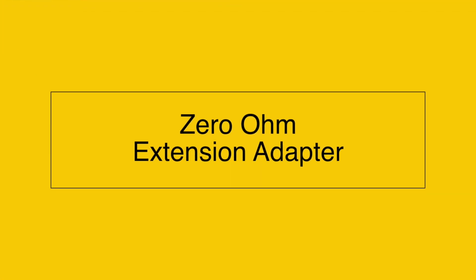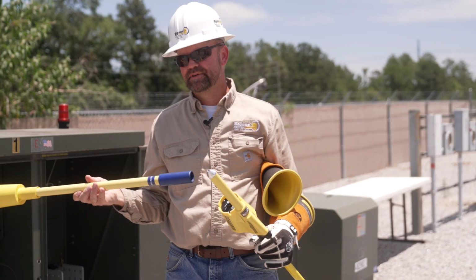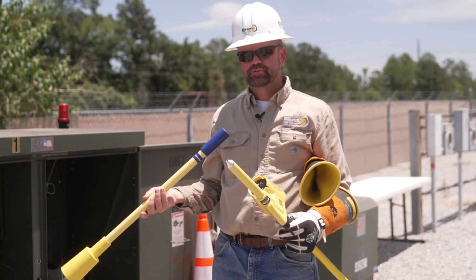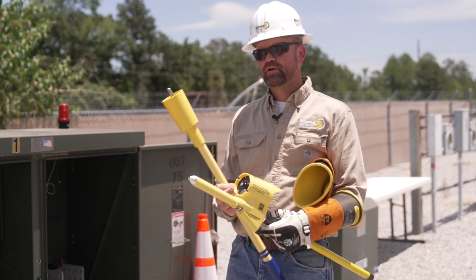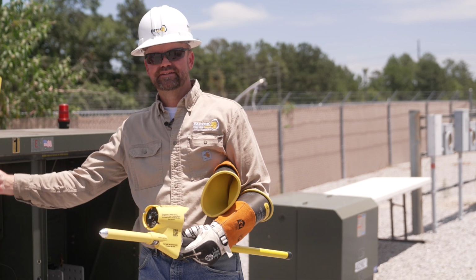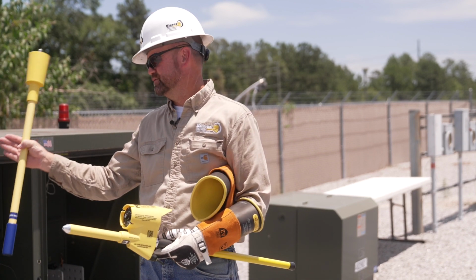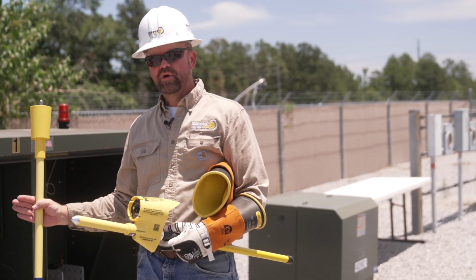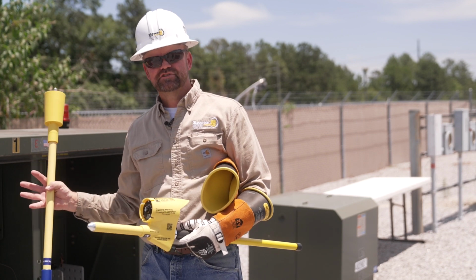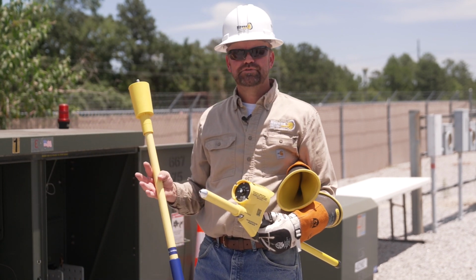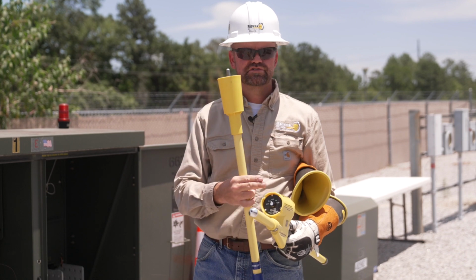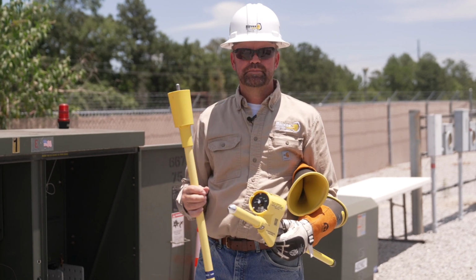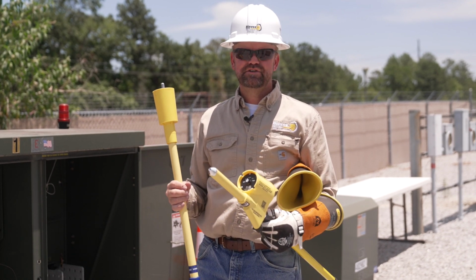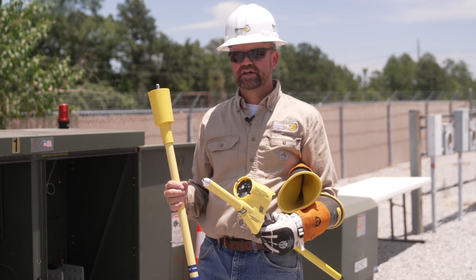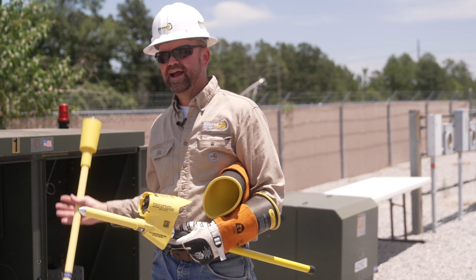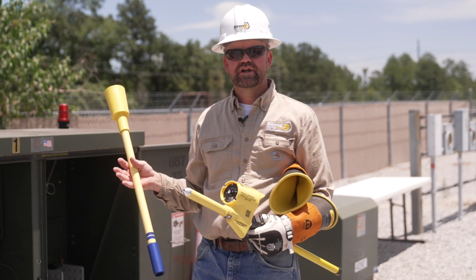Okay, now I want to demonstrate using our 0 ohm extension adapter. And what this will do is it will actually get my housing of my meter probe further away from this ground plane. So the edge of this 3-phase pad mount is all grounded, so that affects the reading of this device in the voltage detector position. So in other words, the URD and OH switch positions, this device is being used as a voltage detector, okay? So I want to get away from grounds that will affect the reading or another phase.